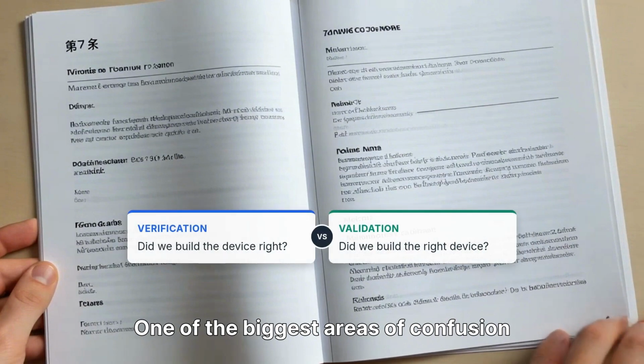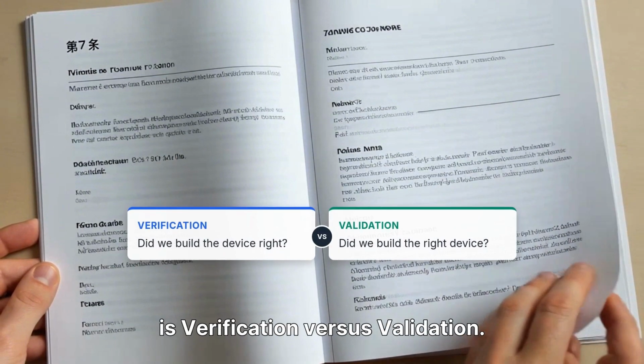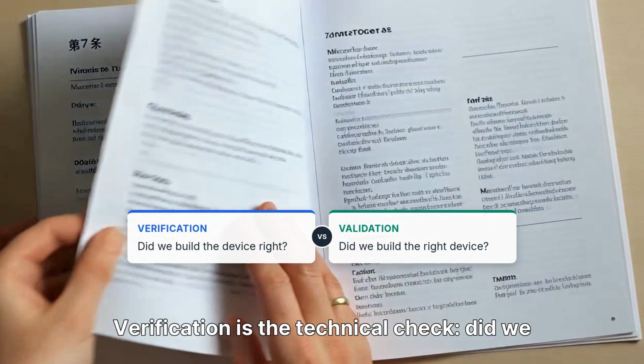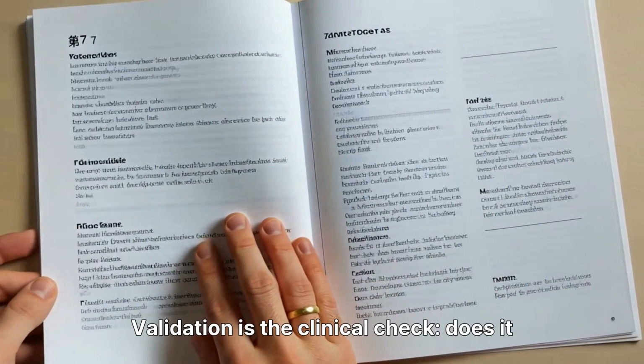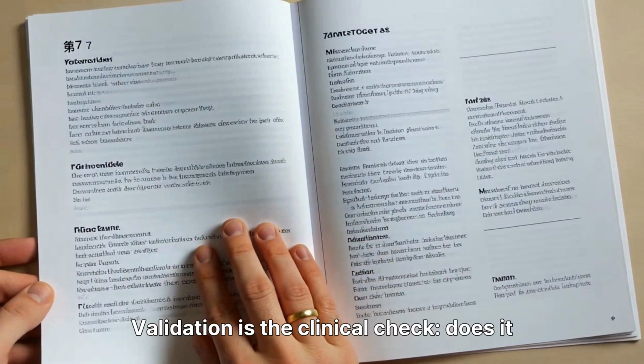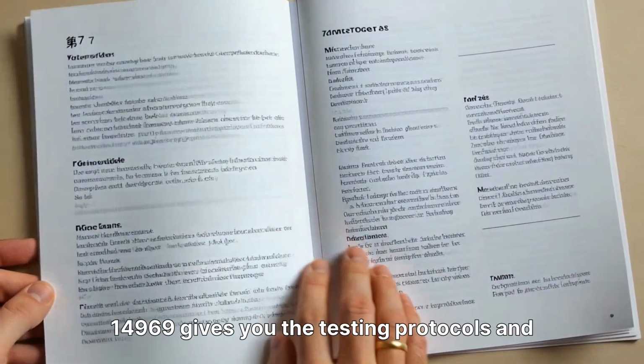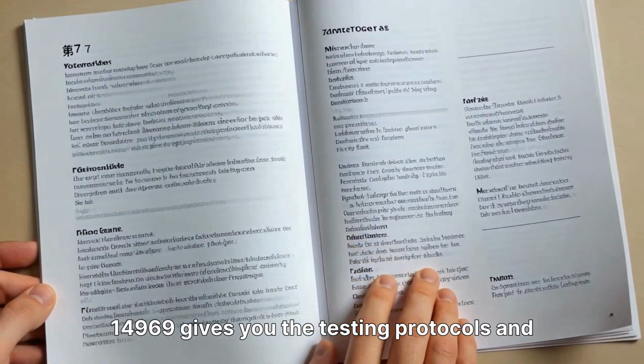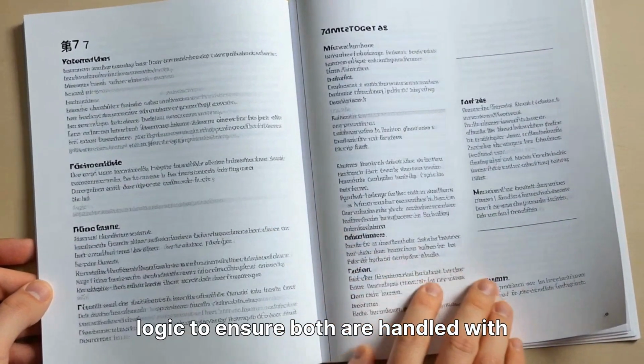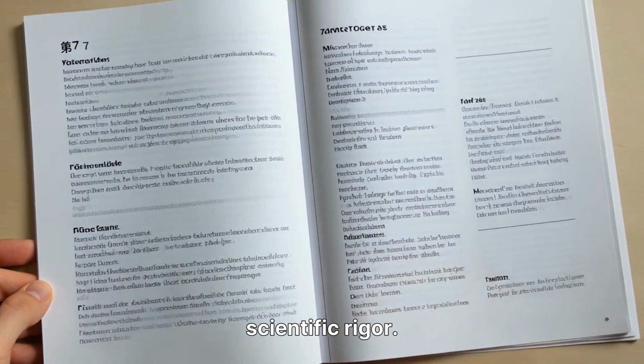One of the biggest areas of confusion is verification versus validation. Verification is the technical check. Did we meet our specs? Validation is the clinical check. Does it work for the user? 14969 gives you the testing protocols and logic to ensure both are handled with scientific rigor.